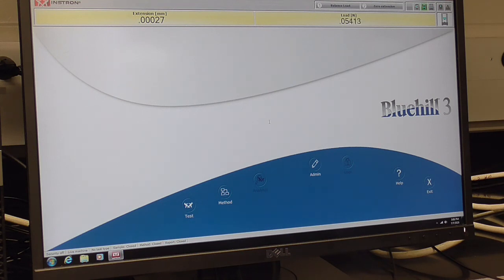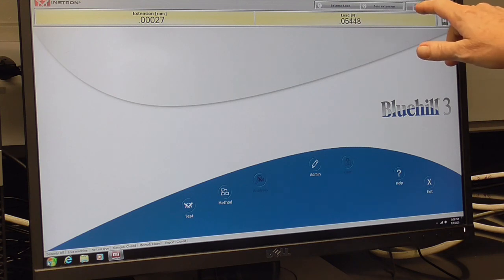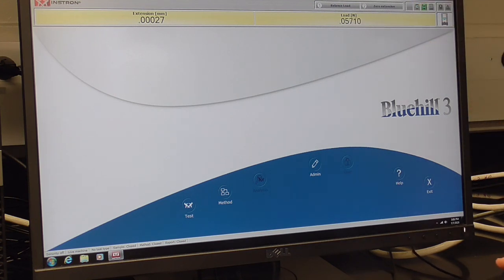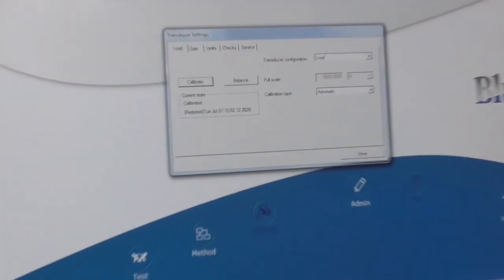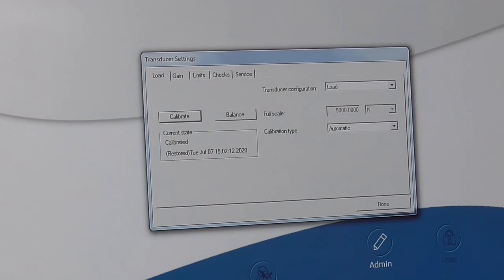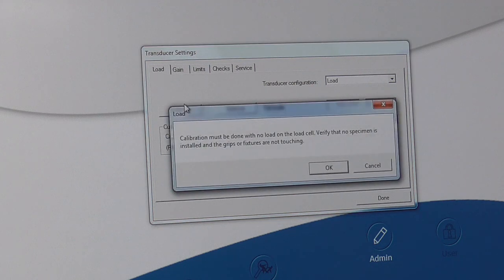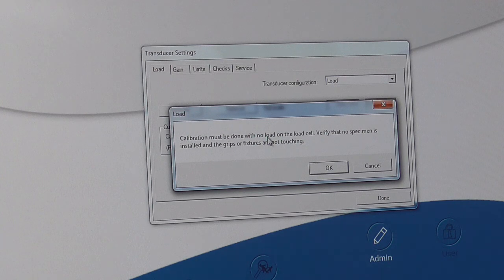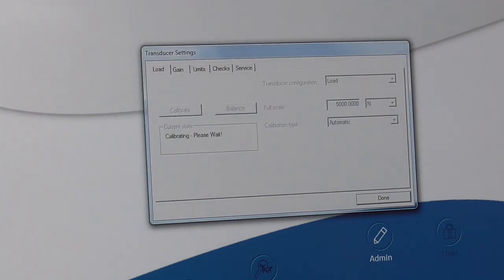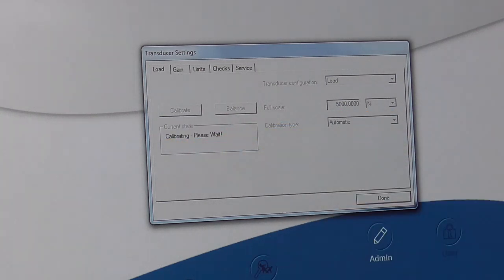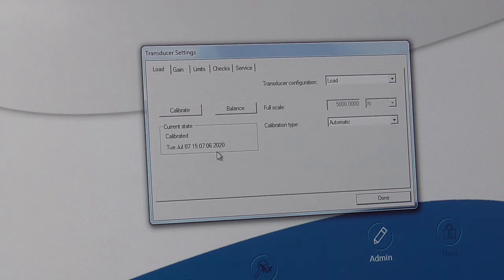The first thing you want to do, if you're the first person to run the instrument, is calibrate the load cell. That icon is up here in the upper right. It looks like a little load cell, so we're going to click on that. The pop-up will come that allows you to either balance the load cell or calibrate. In this case, we want to calibrate, so I'm going to click calibrate. It's warning me that I cannot have a dog bone or any load on the load cell during calibration, and I do not, so I'm going to click OK. It tells me here that it's calibrating. Please wait. And when it's finished, adjusting 0 to 5,000 newtons, 4 to 20 milliamps, it tells me it's finished and when it was calibrated. So now I'm done with the calibrating.